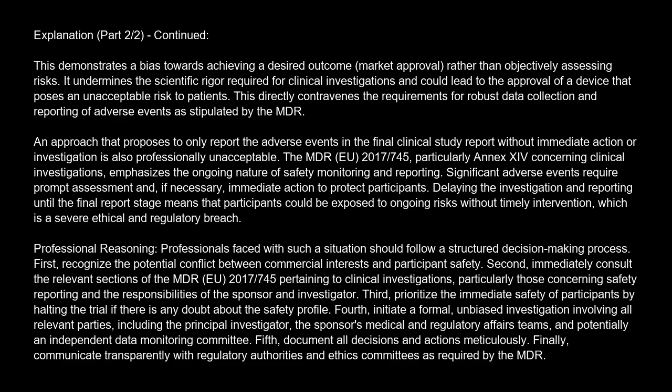Fourth, initiate a formal, unbiased investigation involving all relevant parties, including the principal investigator, the sponsor's medical and regulatory affairs teams, and potentially an independent data monitoring committee. Fifth, document all decisions and actions meticulously. Finally, communicate transparently with regulatory authorities and ethics committees as required by the MDR.